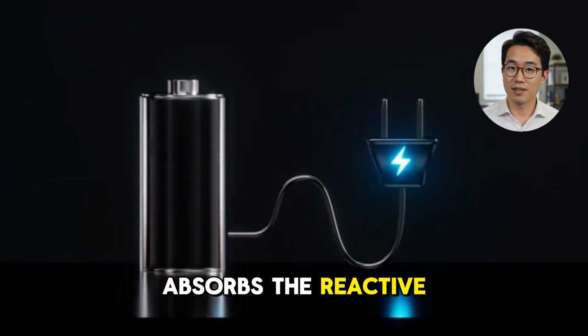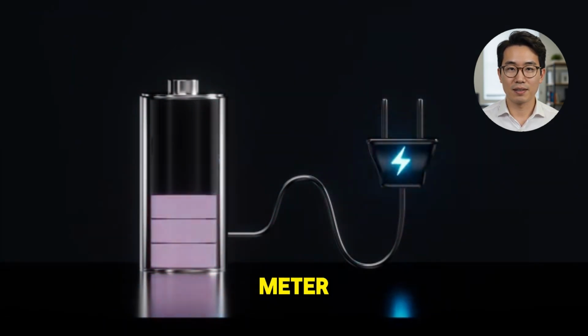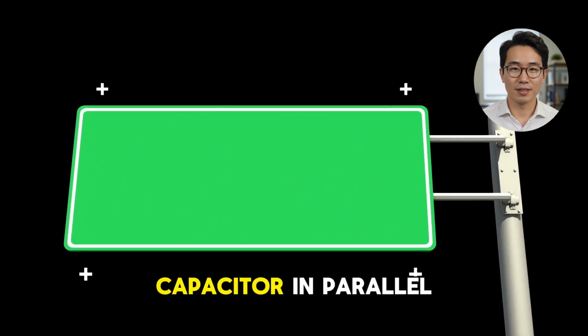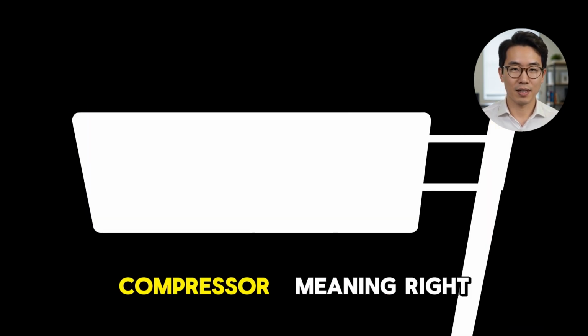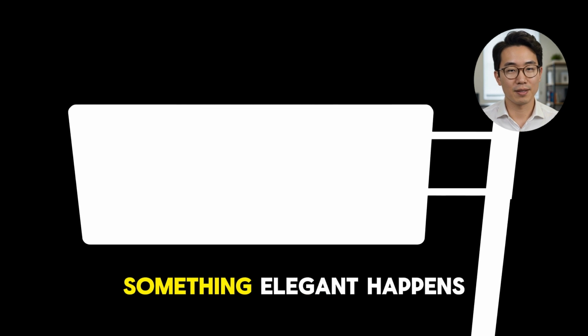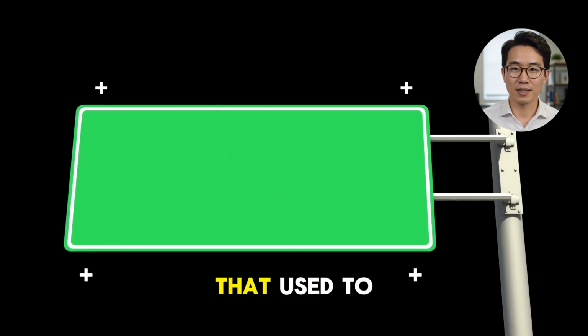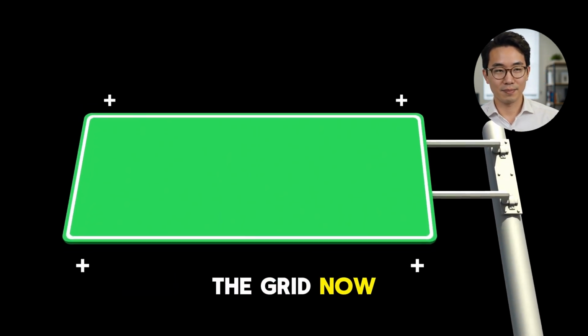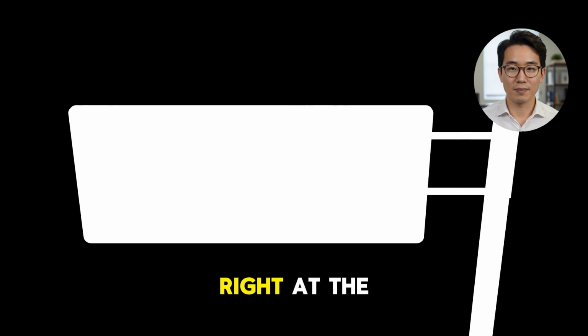It absorbs the reactive current before it bounces back through your meter. When you connect a properly rated capacitor in parallel with your AC compressor, right alongside it in the circuit, something elegant happens. The reactive current that used to flow all the way back to the grid now gets absorbed and recirculated locally, right at the unit.